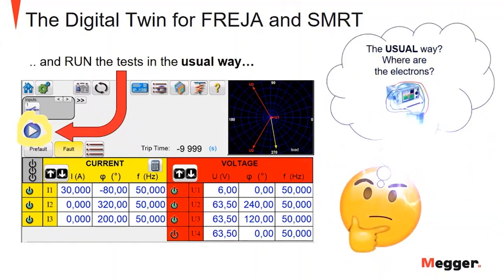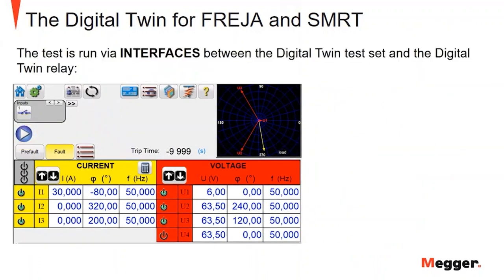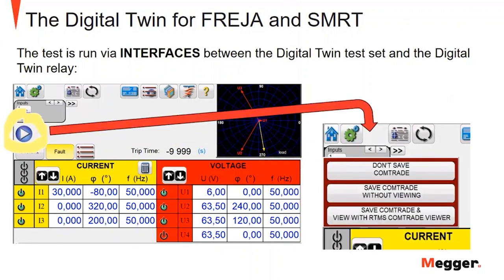Because where are the currents? Where are the voltages? Where are the electrons? And we have to understand that the test is run according to interfaces that have been decided between the digital twin test set and the digital twin relay. Today, at the moment, this interface is ComTrade. So when the digital twin runs, it saves the result of the test in a ComTrade file. Voltage and currents are in the ComTrade file.